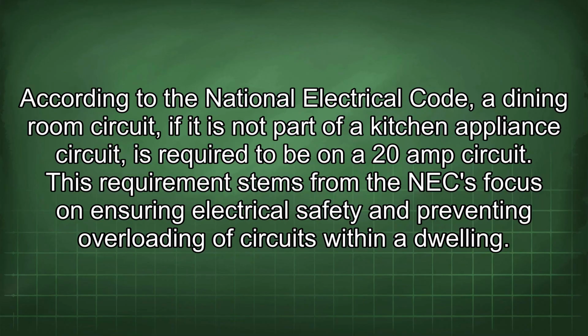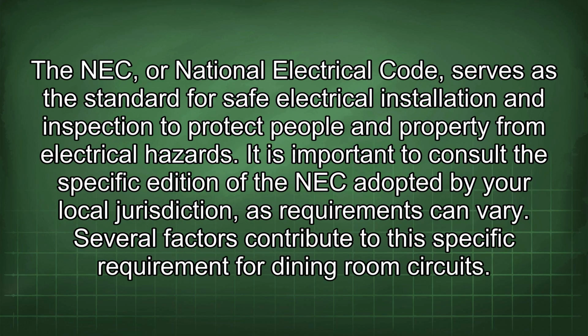According to the National Electrical Code, a dining room circuit, if it is not part of a kitchen appliance circuit, is required to be on a 20 amp circuit. This requirement stems from the NEC focus on ensuring electrical safety and preventing overloading of circuits within a dwelling. The NEC, or National Electrical Code, serves as the standard for safe electrical installation and inspection to protect people and property from electrical hazards.